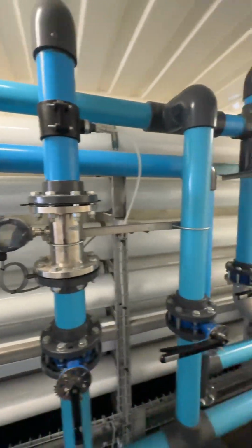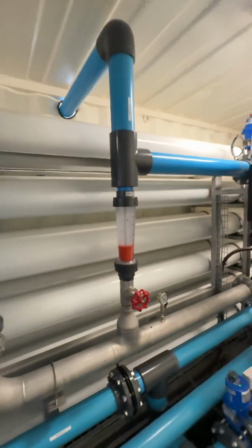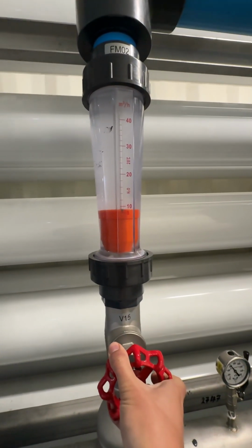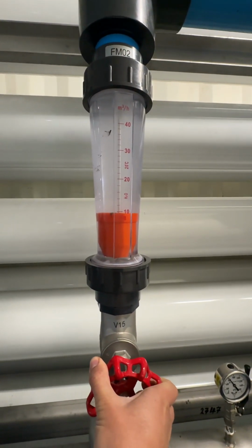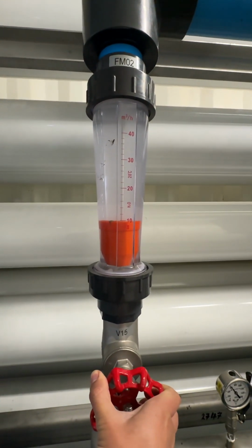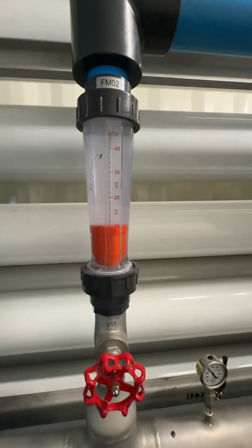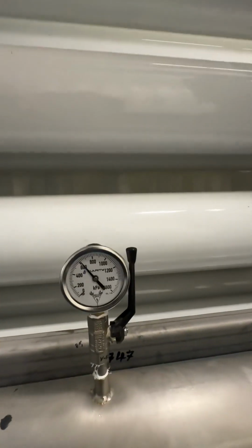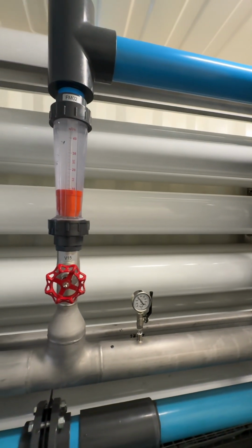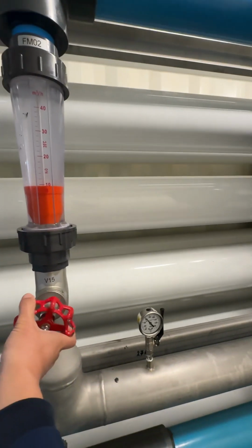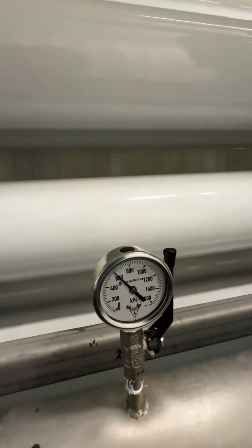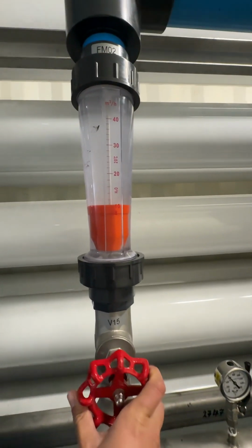See there's 47 cubes an hour. Here this one is at 10 cubes an hour. We can open this a bit more, wastage at 10, so that you have 20% wastage. Here you'll also see the pressure on the discharge line, the waste line, which is quite high. So we're going to open this a bit more, that pressure is going to drop. We don't want that, we want this at 10.